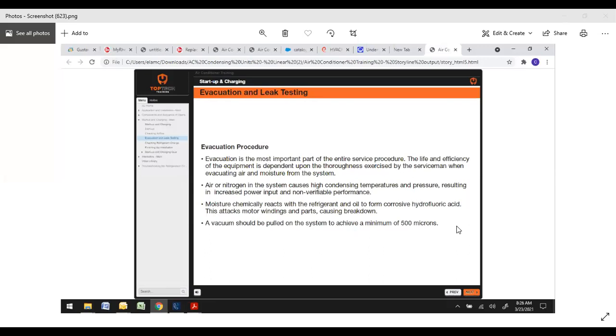Even the few extra minutes that takes, and then your vacuum pump. I know guys that used to change their vacuum pump oil at the beginning of every summer and let it roll all summer long. If you're in the field, service, installation, we do get paid by the hour, by the job, but it is important to do a good, thorough job. Vacuum pump oil is cheap. Once it gets clogged with contamination, it has to work 4 and 5 times as long, and it'll never suck it down like it's supposed to.